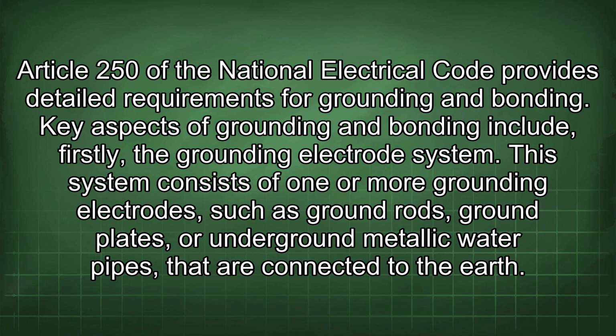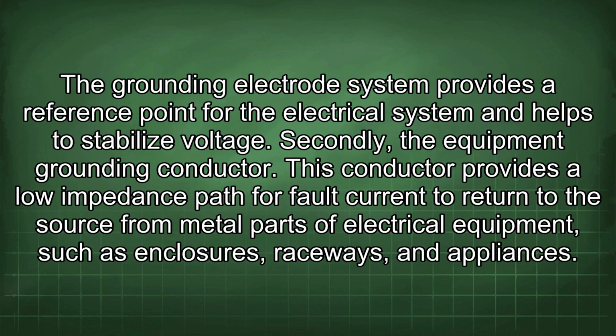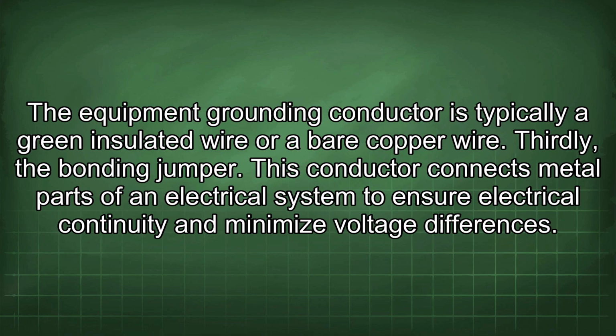Key aspects of grounding and bonding include, firstly, the grounding electrode system. This system consists of one or more grounding electrodes, such as ground rods, ground plates, or underground metallic water pipes, that are connected to the earth. The grounding electrode system provides a reference point for the electrical system and helps to stabilize voltage. Secondly, the equipment grounding conductor. This conductor provides a low impedance path for fault current to return to the source from metal parts of electrical equipment, such as enclosures, raceways, and appliances. The equipment grounding conductor is typically a green insulated wire or a bare copper wire.